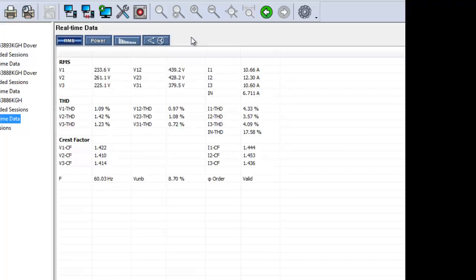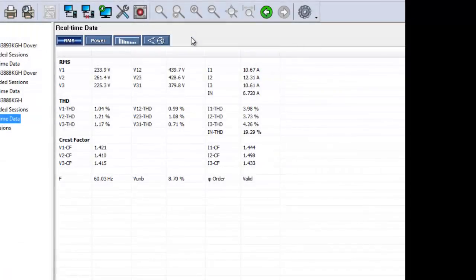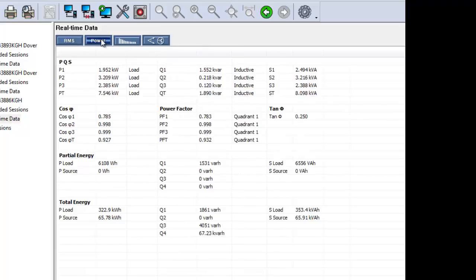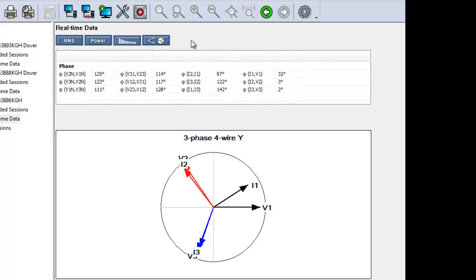The DataFrame now displays real-time measurements from the PEL. When the distribution system currently under measurement is AC, four buttons appear at the top of the data frame. These buttons do not appear when measuring DC systems. RMS displays root-mean square channels, including RMS, THD, and Crest Factor. Power displays power channels, including PQS, partial energy, total energy, and others. Harmonics displays harmonics channels. Phasor displays the phasor diagram for the distribution system currently under measurement.